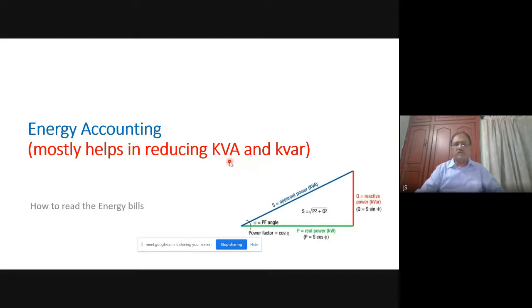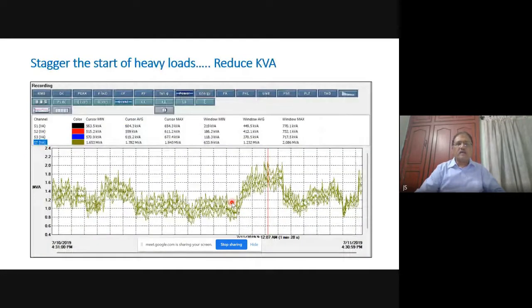So therefore, when we talk about reducing KVA and KVAR, we will be addressing energy cost. See, actually today, I've taken a few cases as an example. If you see this industry where we did an audit, during morning hours when the shift starts, when most of the equipments are started, the KVA registers the maximum. But you see the window max and you see the average.